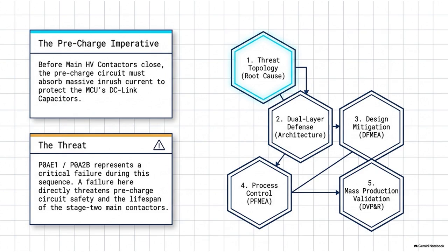And in the mechanical world, if you introduce that much sudden force to a dormant system, things snap. But in the electrical world, I imagine the points of failure here are the main contactors themselves. Precisely. Those main contactors are electromechanical relays. So as those metal contacts physically move toward each other to close the circuit, that massive potential difference will actually ionize the air gap between them before they even physically touch. Oh, wow. So the electricity just jumps the gap. Yeah, you get a high-energy plasma arc. And that arc vaporizes the metal plating on the contacts. So when they finally do slam together under the force of the solenoid, they're swimming in a pool of molten metal.